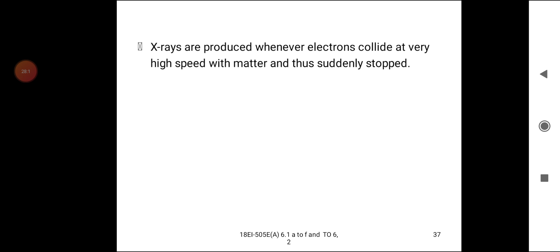The X-rays are produced whenever electrons collide at a very high speed with matter and thus are suddenly stopped. X-ray tube is basically a high vacuum tube. X-ray tube is basically a high vacuum diode, a heated cathode located opposite to a target anode. The diode is operated in the saturated mode with a fairly low cathode temperature. The current through the tube does not depend on the applied anode voltage.